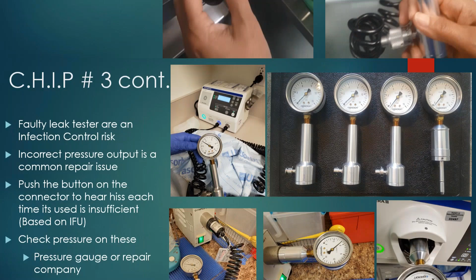So to continue with that, what we're finding is that faulty leak testers are definitely an infection control risk, and it's all over the place. Incorrect pressure output is a common repair issue. Basically, you push the button on the connector to hear this hissing noise each time it is used, but it's really insufficient based on the IFU. Checking the pressure on these pressure gauges will tell you if it's meeting that. For example, in the Olympus IFU, in translation of the numbers in there, it will say 4.1 PSI, or that number or less, is a failure. You're not getting enough pressure.